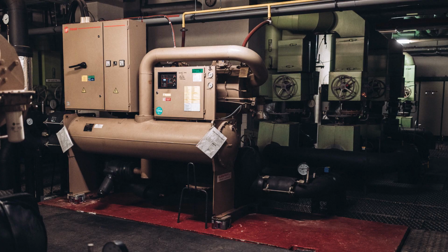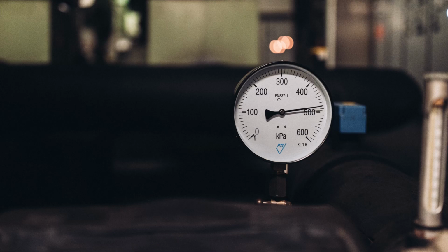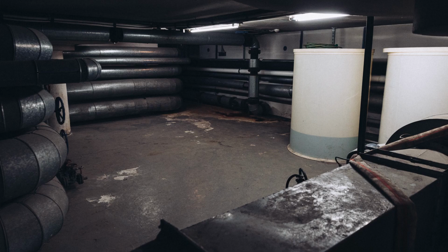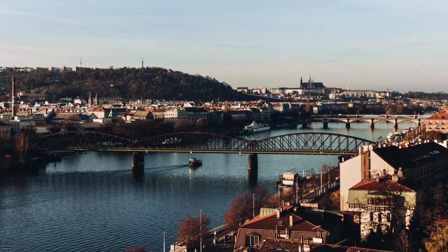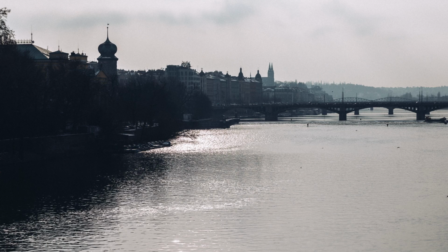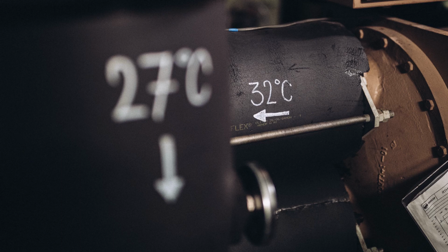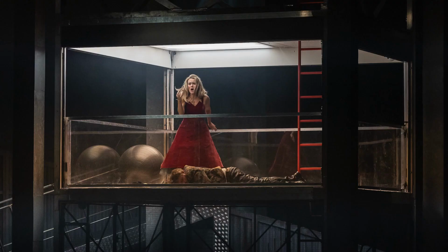The system is made up of 3 heat pumps, 2 larger and 1 smaller, as well as a chiller which is used for cooling. The larger ones utilize water from the Vltava and increase the water's temperature to warm the theater. The smaller one extracts heat from the oil used for the stage's hydraulic system.